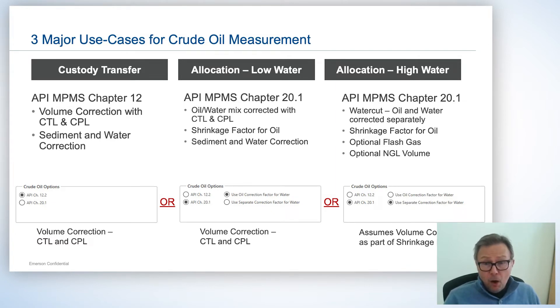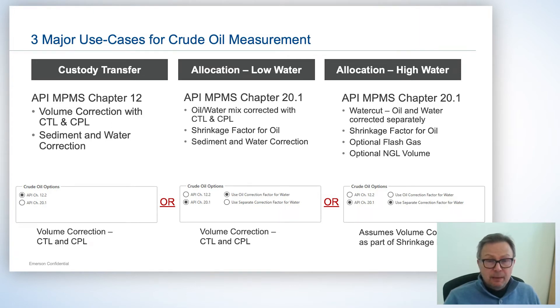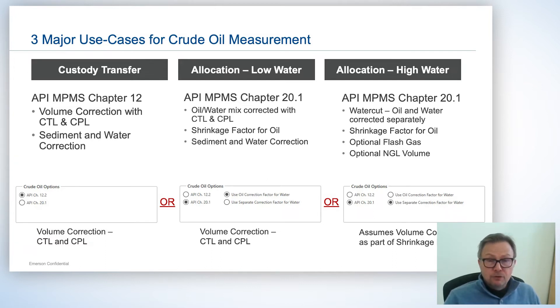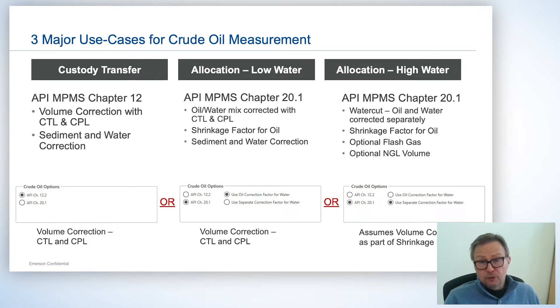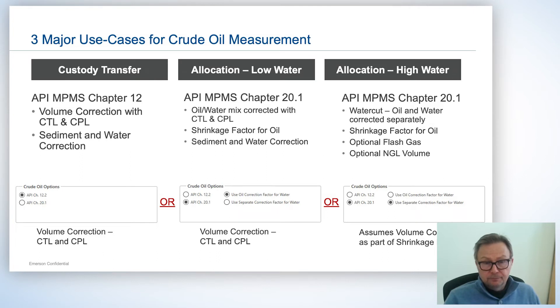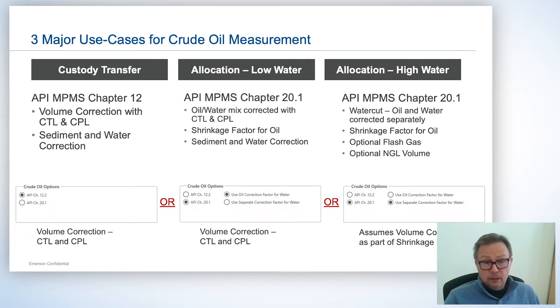The allocation high water method, as its name implies, is used where you have a much higher percentage of water in the oil. In this method we actually separate the oil from the water, then apply a temperature correction to the water and a shrinkage factor — which would typically include pressure and temperature correction — to the oil. We apply those corrections separately to produce our oil and water flow rates and totals. The default in our products is the custody transfer method, but the allocation method is there if you need it.